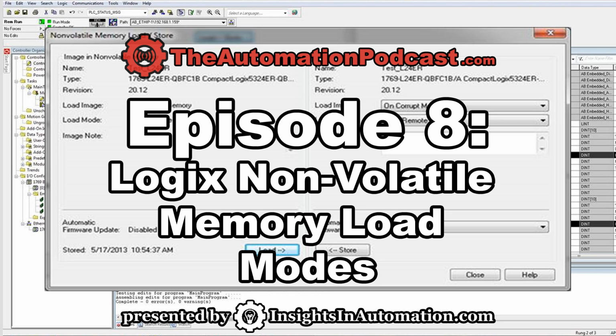The final load mode is on corrupt memory. And this is very popular because what this says is if my PLC's memory is corrupt, i.e. scrambled somehow, maybe a power surge or whatever, then I will load my memory from the non-volatile image.